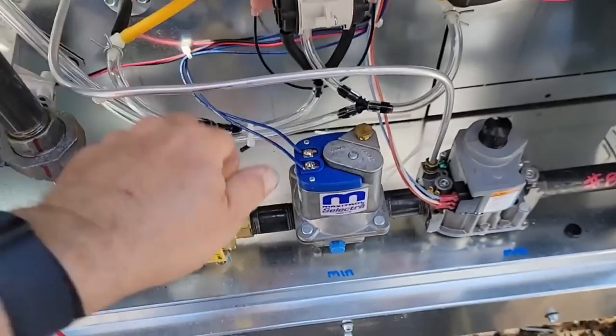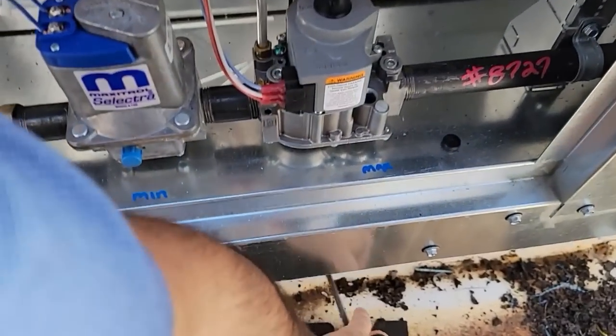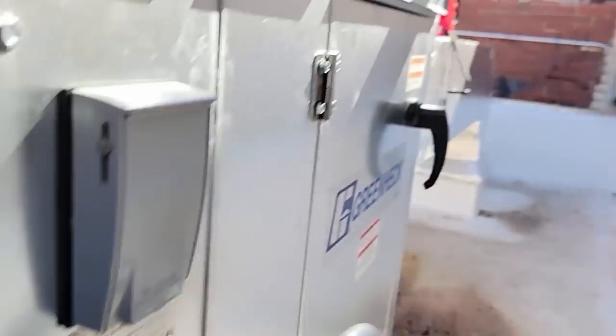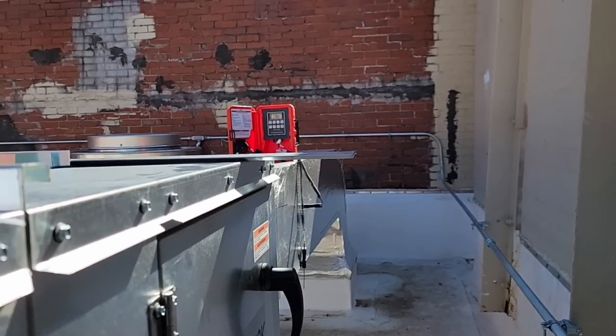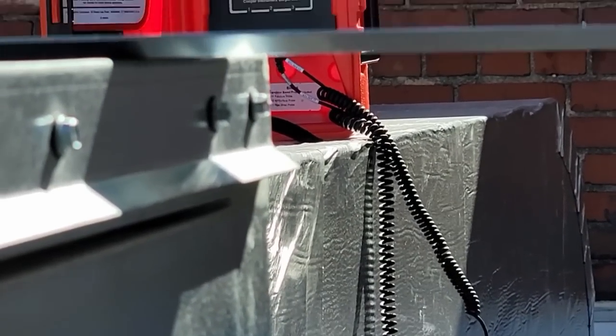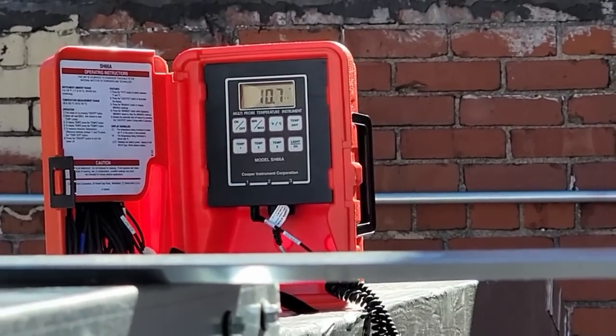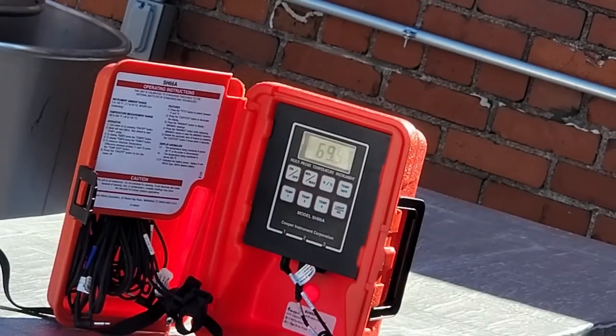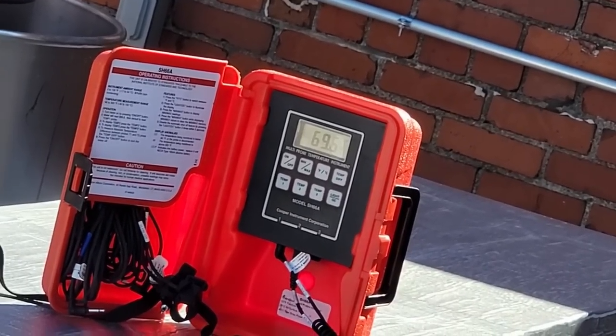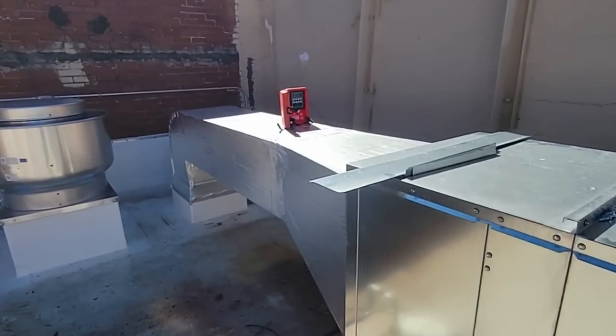Let's go ahead and open this up. So we got that open. Watch our temp down there. Climb up to 70. And then we should be good. Okay, 69.4. I'm happy with that. I don't want to go too much more. So we can go ahead and see what our total output temperature is. We just hit a different pitch there. Something got shut down. They probably shut it off downstairs.